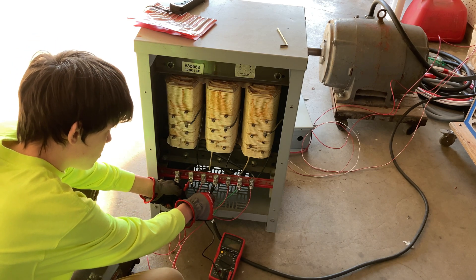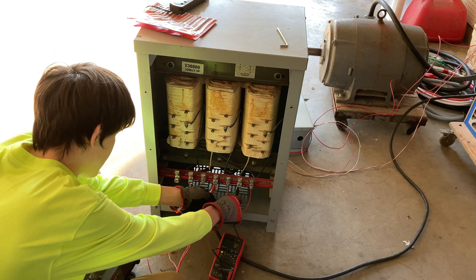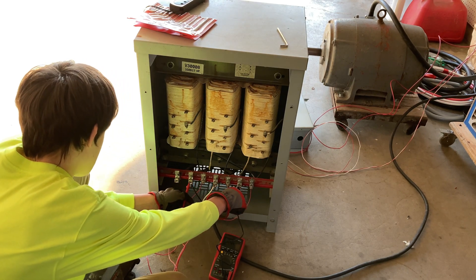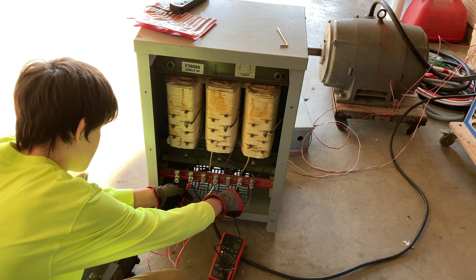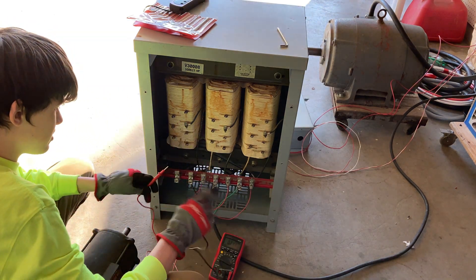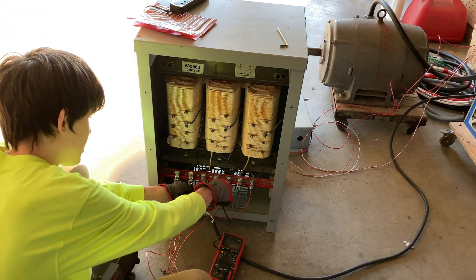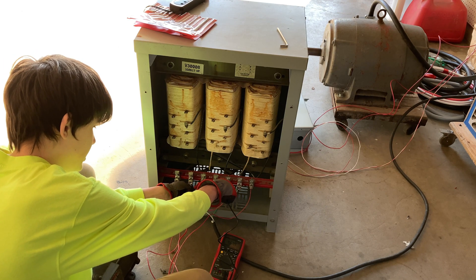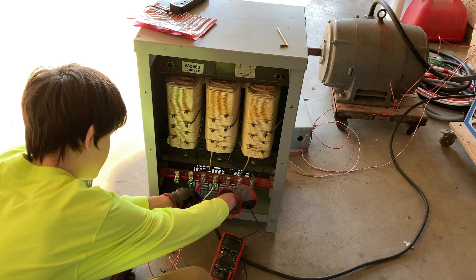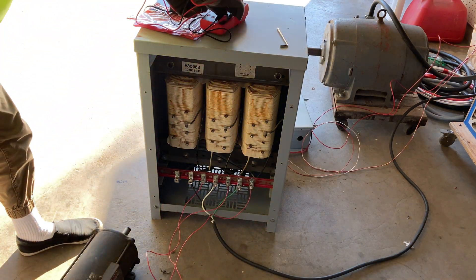Between line one and line two — just from the power grid — we have 245 volts. Between line two and line three — the power grid and my generated leg — we have 242 volts. Between line one and my generated leg, it's 240 volts. They're really close; without the run capacitors those voltages would be way different — they're within just a couple volts of each other. The output of the transformer gives 467 volts, 462 volts, and 457 volts — not perfect, but good enough to run a motor.